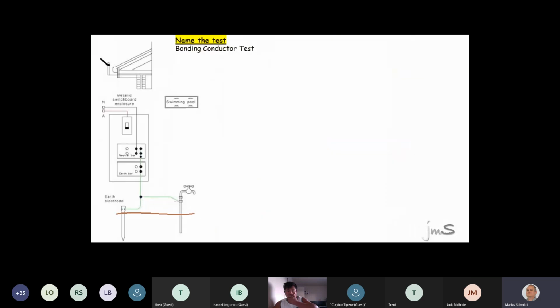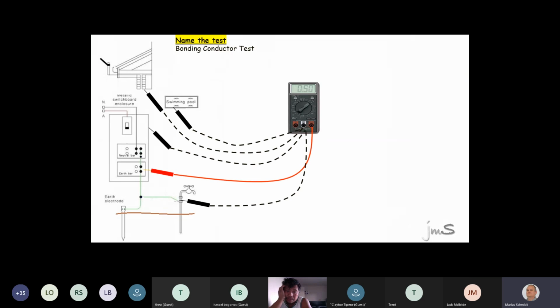Right, guys, for bonding, you put it on the earth bar and you measure to any other bonding conductors where it's supposed to go. You all agree that anything which is metal must be earthed. Now, guys, I'm not a person who knows my building codes very well. However, the building code states that if you've got suspended ceilings, the bars which keep the suspended ceiling up must be bonded. See this upstairs where you look in the room? Do you know what's rondo? Building code says you shall earth or bond the rondo as well. What size wire? Right, 4 mil or greater, correct.